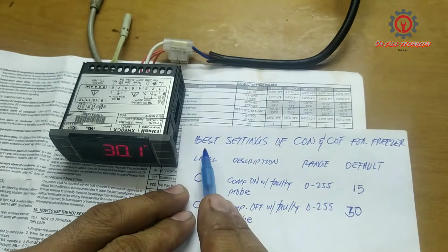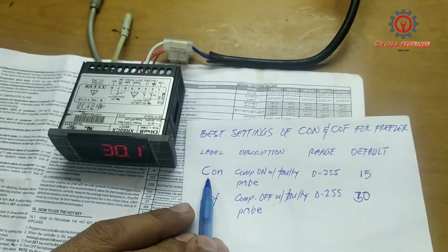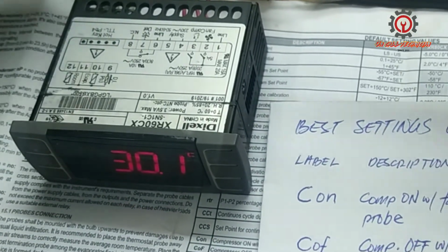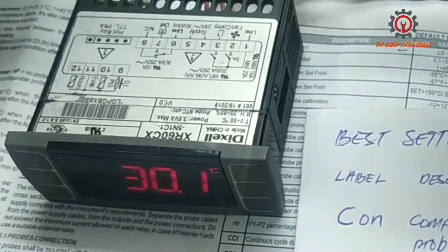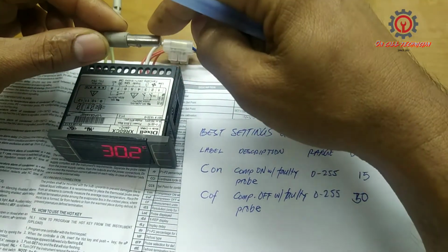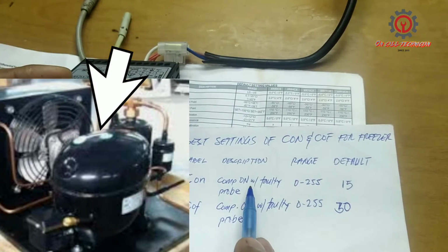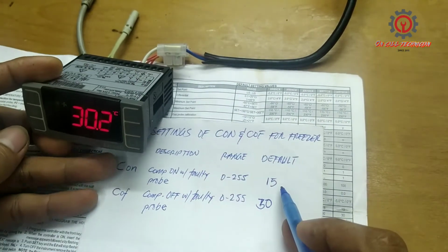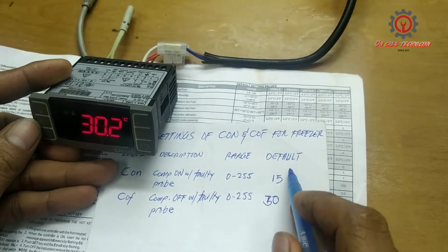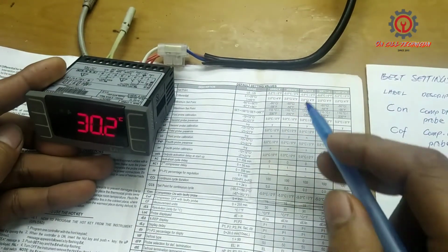Today I'm going to teach you the best settings for C-on and C-off for freezer setting. And C-on, guys, is compressor on with faulty probe, and this is our room sensor, and this is the thermostat. In case of abnormality, the compressor will stay on with a default of 15 and compressor off with a default of 30 minutes.